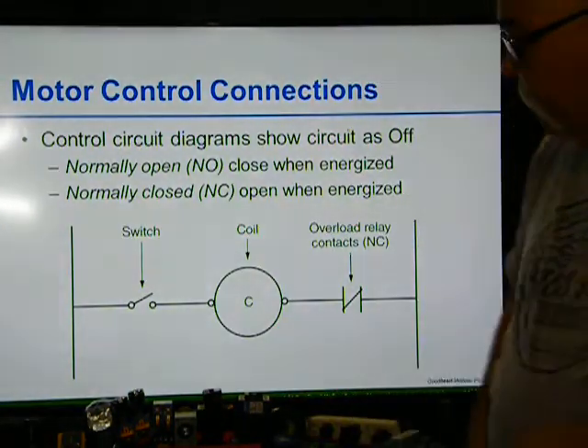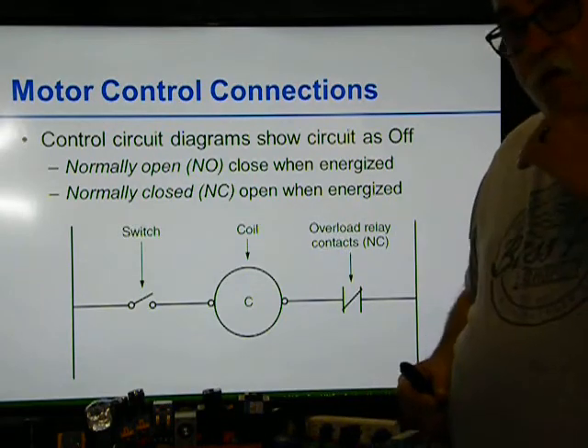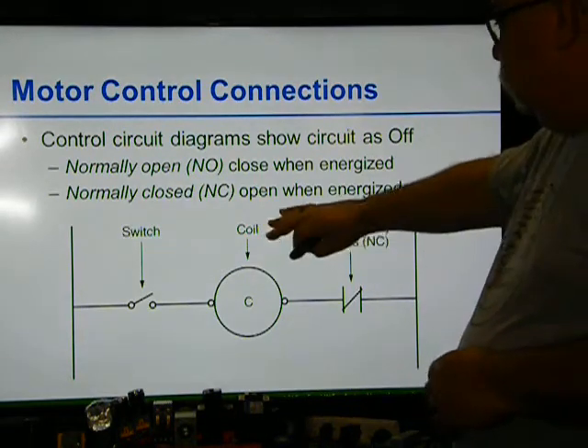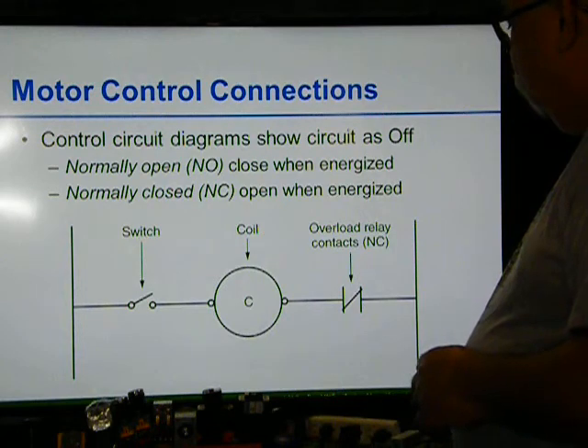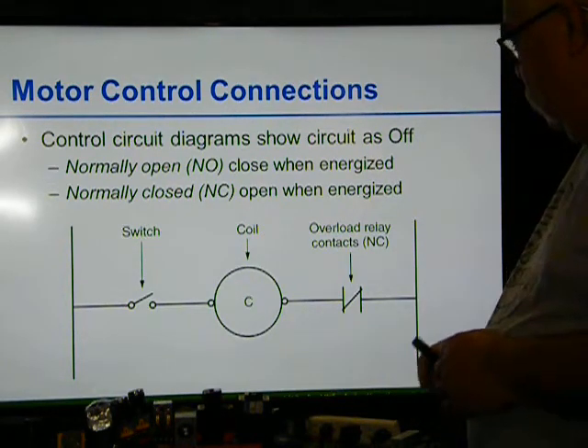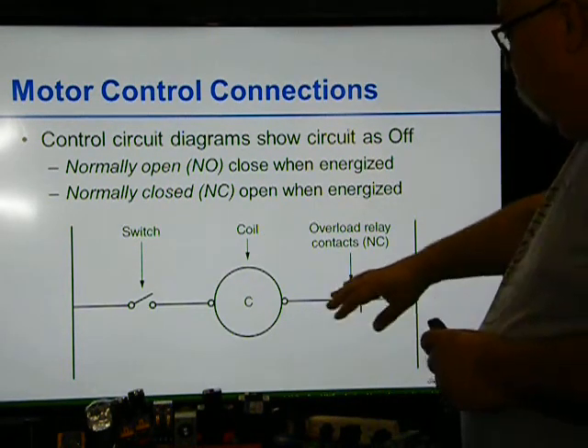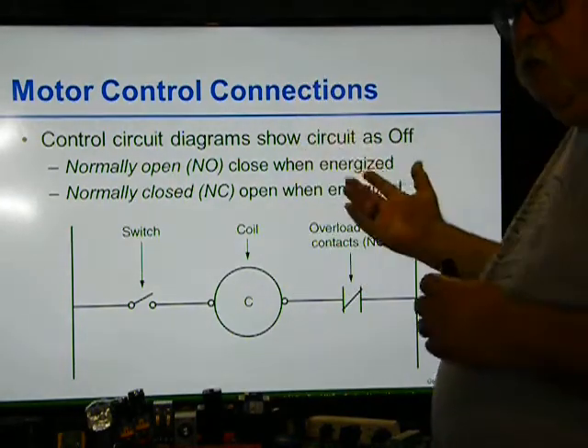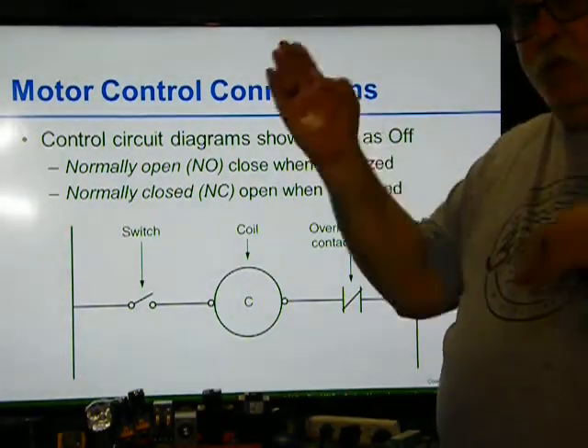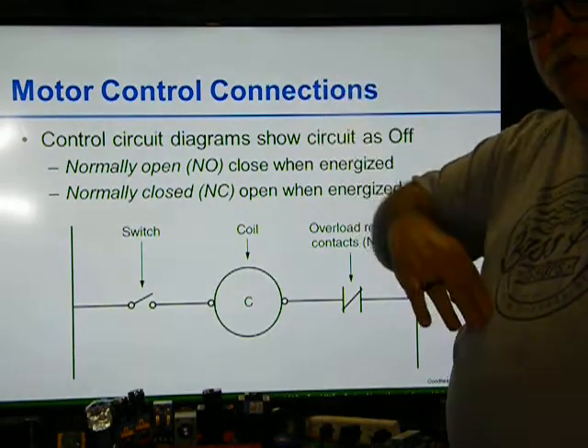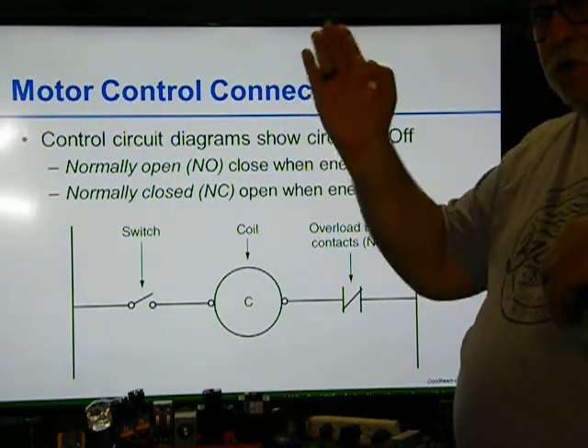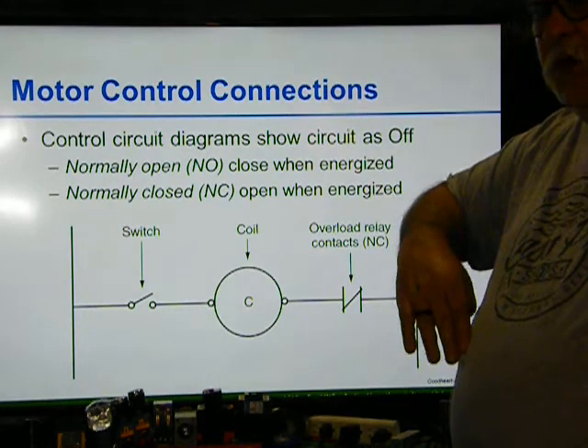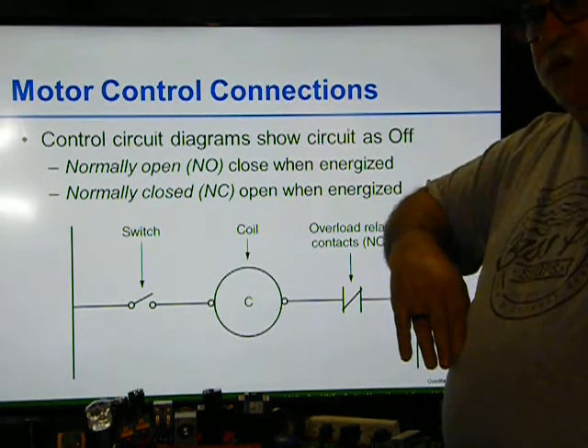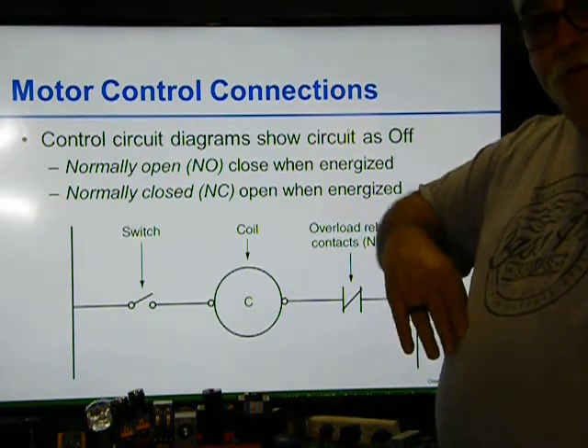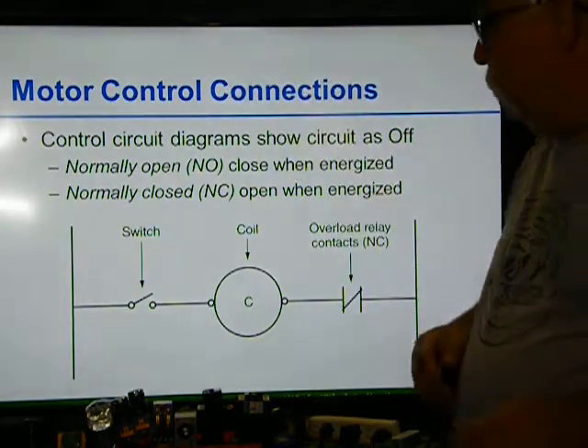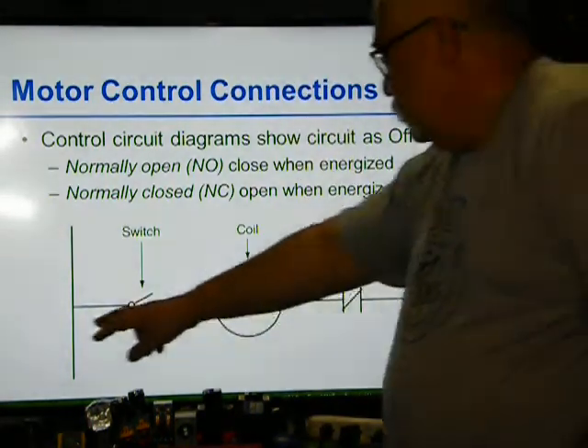You connect them a little different, but normally closed, open when energized. So again, this power may be sensing from somewhere else, and it keeps it open. And you have it that way, so let's say you have two motors on a circuit, they both don't run at the same time. So one is always off, one is always on. So when you turn the switch on and it gets energized, the switch opens and turns that one off, and it turns this one on. And here's showing the switch.